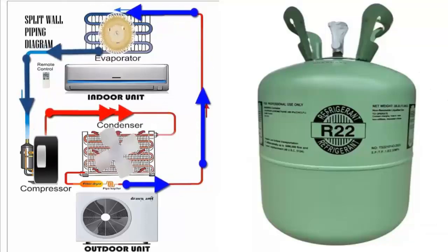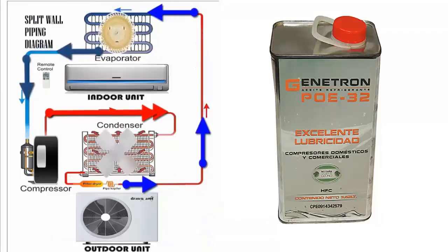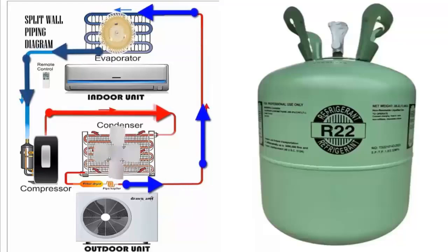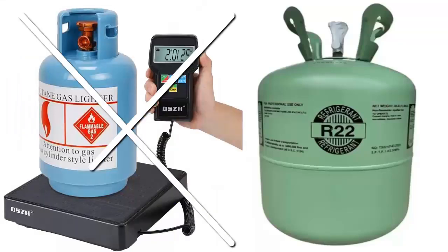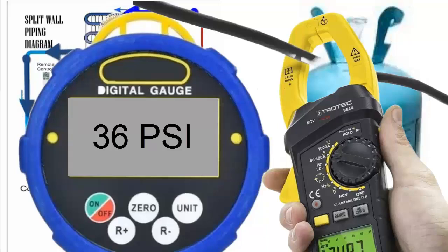4. It is essential to change the R22 compressor oil to POE-type oil when using R134a. 5. The recharge can be done in liquid or gas phase. Do not recharge by weight, but rather develop the charge until the operating pressure of R134a is reached. Constantly check with a clamp meter to ensure the current consumption does not exceed the original equipment's nominal current value.